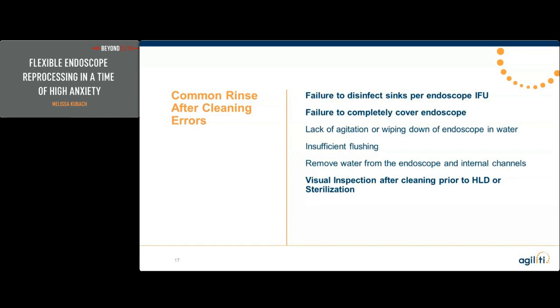I also find, once again, failure to completely cover the whole endoscope. It has a theme, this is a theme. And, of course, visual inspection that everyone knows is required under magnification at the end of the manual cleaning process, before the endoscope moves on to high-level disinfection or sterilization.